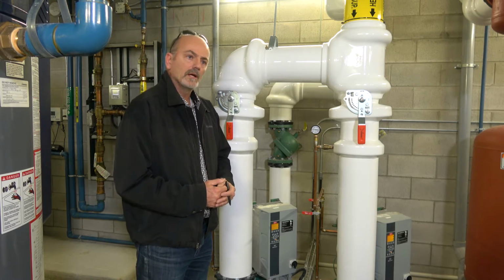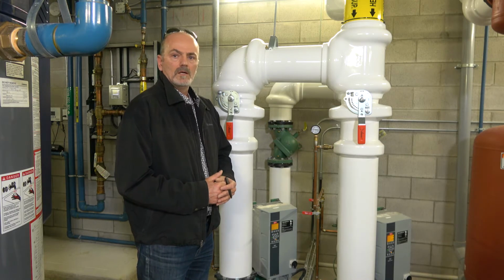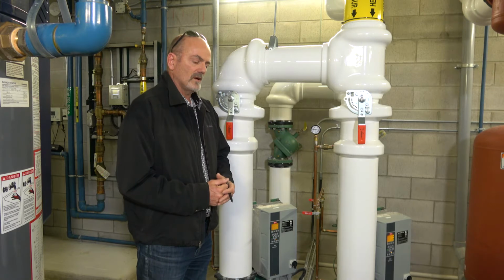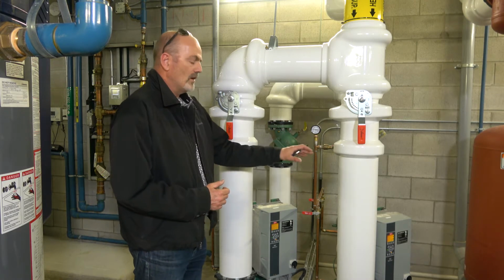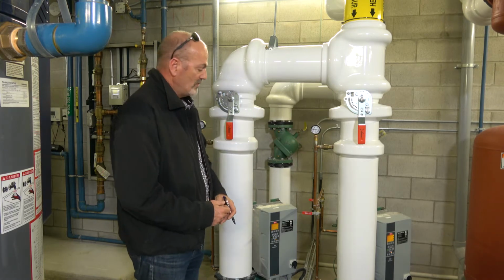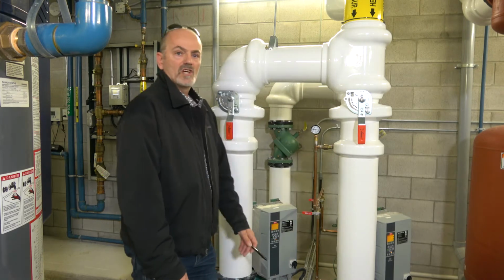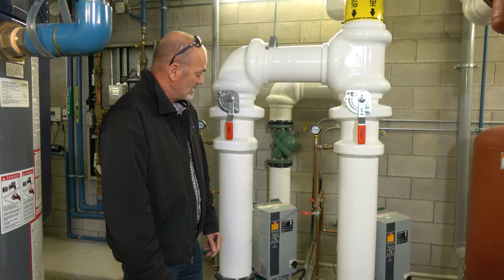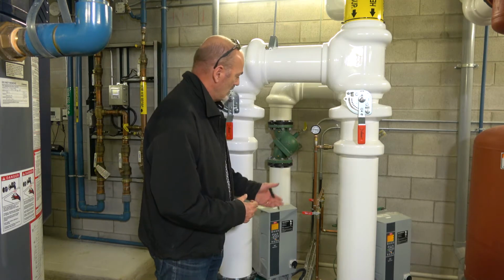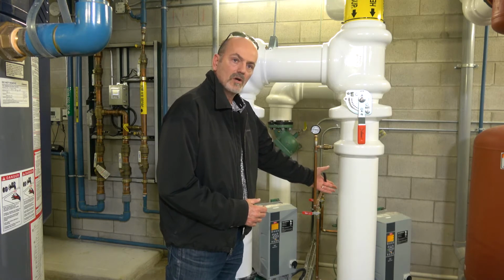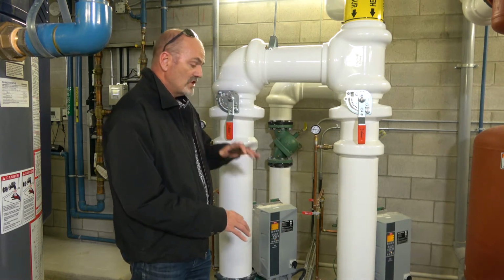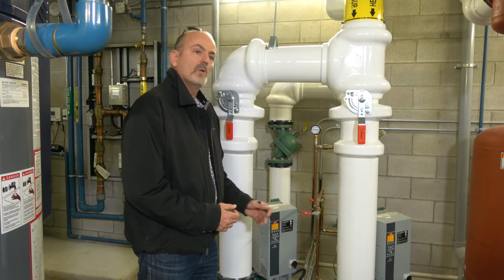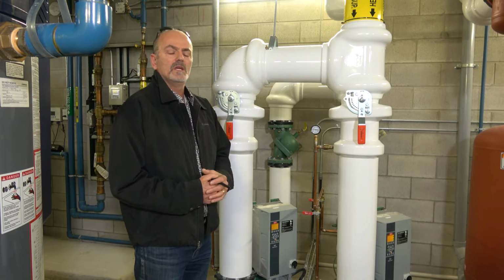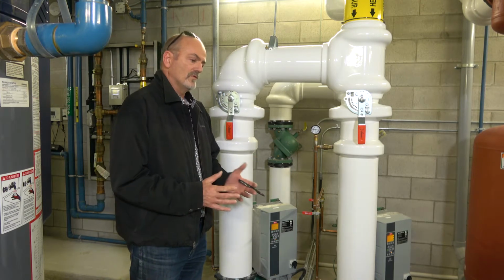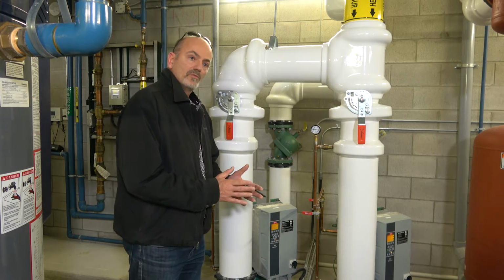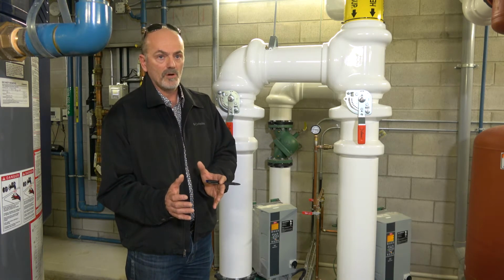All the fan coils out in the building have both two-way and three-way control valves. So what that means is the system pressure out in the building that's sensed by these pumps goes up and goes down. So these pumps are each equipped with self-sensing variable frequency drives. These drives are designed so that they understand the relationship between the motor horsepower and its amp draw and the system pressures. The VFDs respond to that change, so that we'll always have what would be considered constant pressure out into the system. So as valves close, pressure tends to go up, so the drives respond, slow the pump down to match and maintain pressure down a system curve.